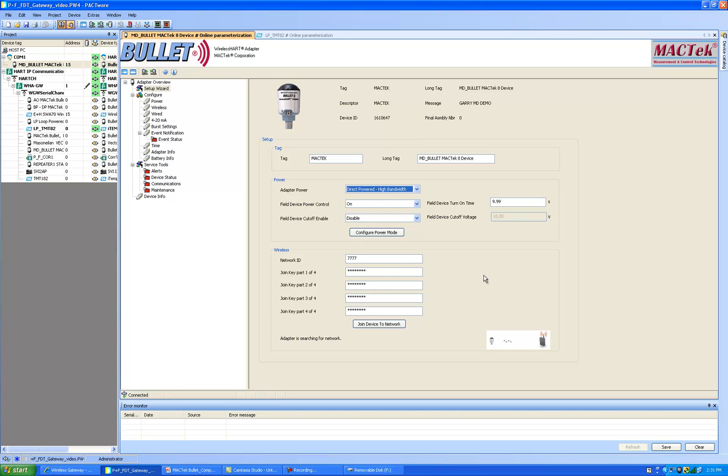The critical steps for us right here is to get this on the network. My network ID is 7. You can see the bullet was set to 7777. So I'm going to make this a 7 and then my join key is simply 0, 0, 0, 0 and the last digit is 7. Typically for wireless HART applications the join key will be complex four eight-character hexadecimal words. Then I just have to select join the device to the network.